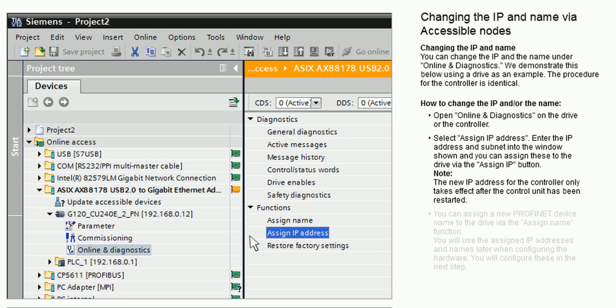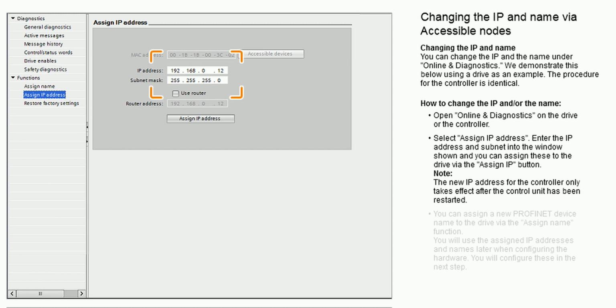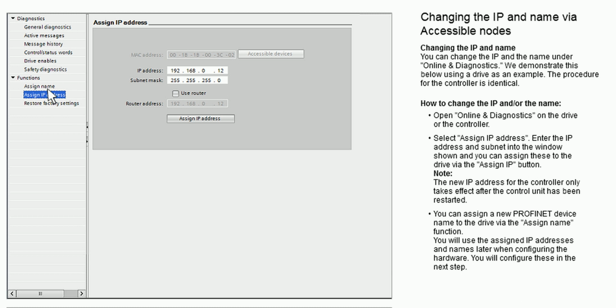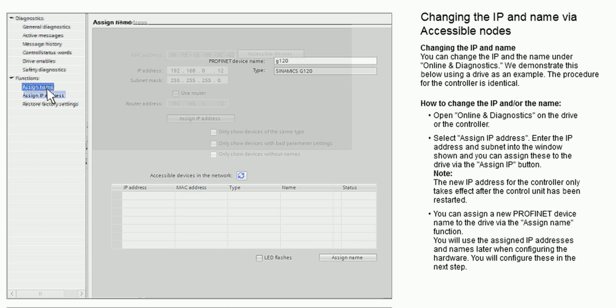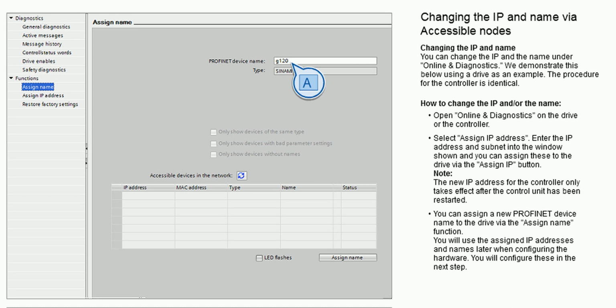Select Assign IP address. Enter the IP address and subnet into the window shown, and you can assign these to the drive via the Assign IP button. Note: the new IP address for the controller only takes effect after the control unit has been restarted. You can assign a new Profinet device name to the drive via the Assign Name function. You will use the assigned IP addresses and names later when configuring the hardware. You will configure these in the next step.